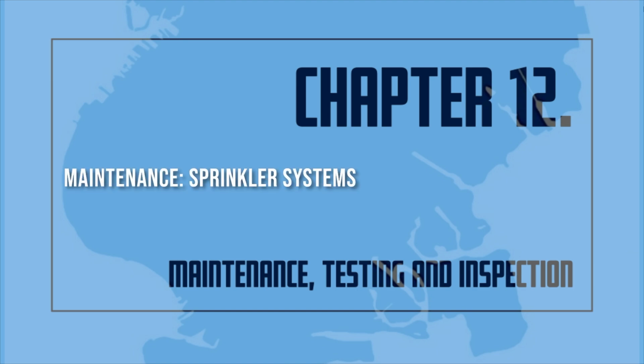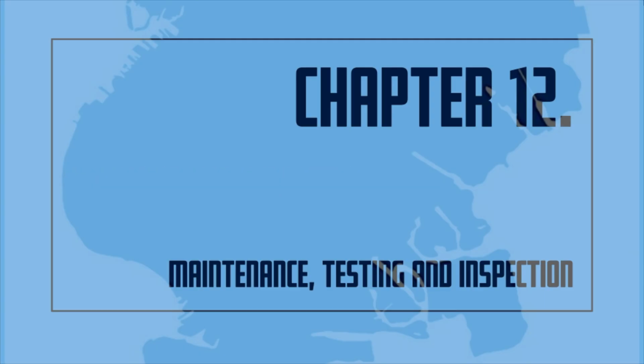3. Maintenance. A. Sprinkler systems. Obstruction investigation. An investigation of piping and conditions shall be done every 5 years by opening a flushing connection at the end of one main and by removing the sprinkler toward the end of one branch line for the purpose of investigating for the presence of foreign organic and inorganic material. Low point drain, dry pipe system. Shall be drained after each operation and before the onset of freezing weather conditions.